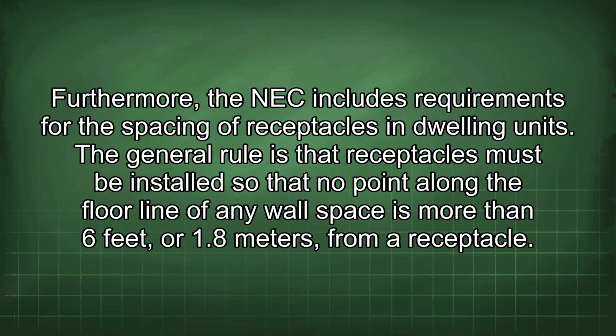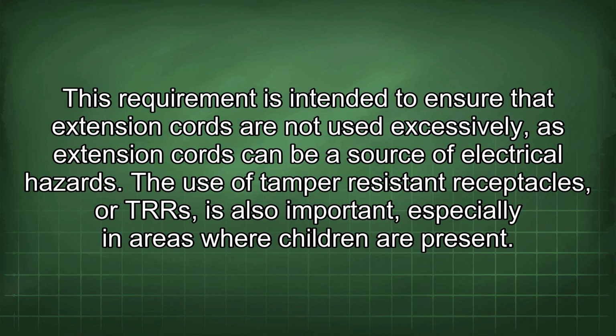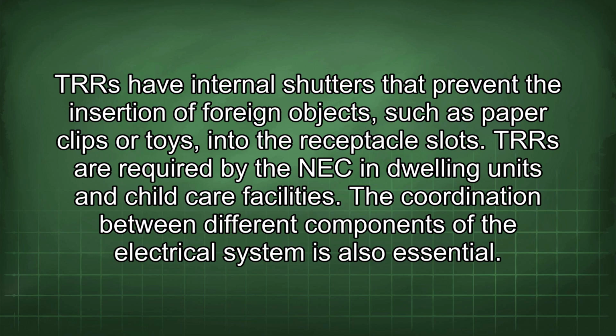Furthermore, the NEC includes requirements for the spacing of receptacles in dwelling units. The general rule is that receptacles must be installed so that no point along the floor line of any wall space is more than 6 feet, or 1.8 meters, from a receptacle. This requirement is intended to ensure that extension cords are not used excessively, as extension cords can be a source of electrical hazards. The use of tamper-resistant receptacles, or TRRs, is also important, especially in areas where children are present. TRRs have internal shutters that prevent the insertion of foreign objects, such as paper clips or toys, into the receptacle slots. TRRs are required by the NEC in dwelling units and childcare facilities.